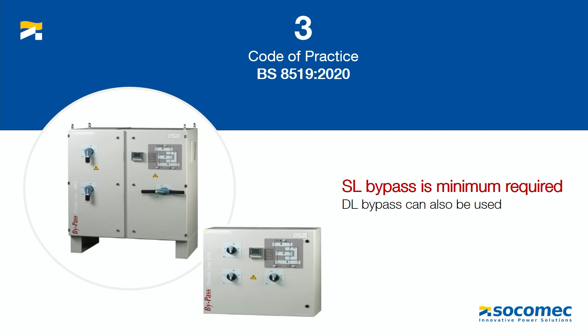You should also consider a dual line bypass. That has a lot of benefits, such that if you were carrying out maintenance and you were to lose your primary source, you would still have the ability to supply your critical load through source 2. So the standard says single line is a minimum, but we now see a lot of consultants specifying dual line because of the added safety benefits.